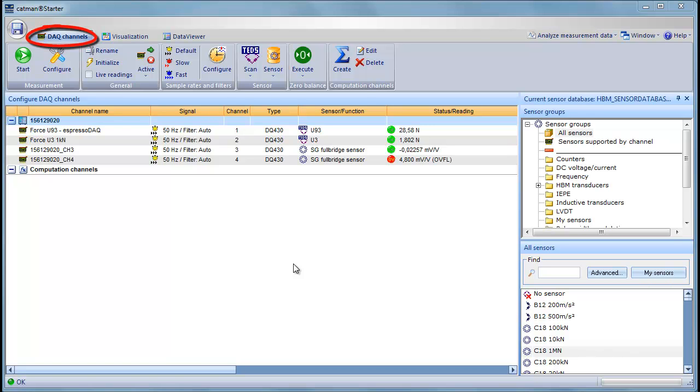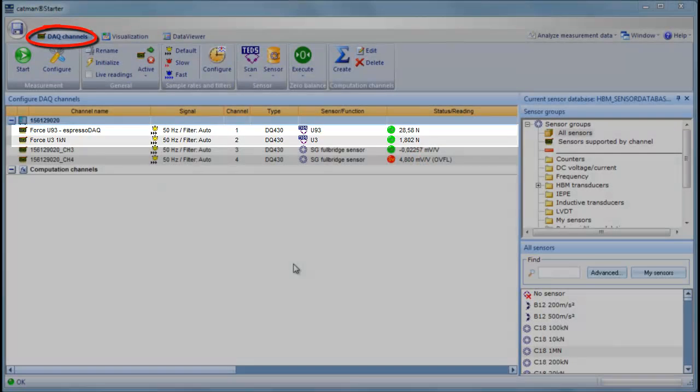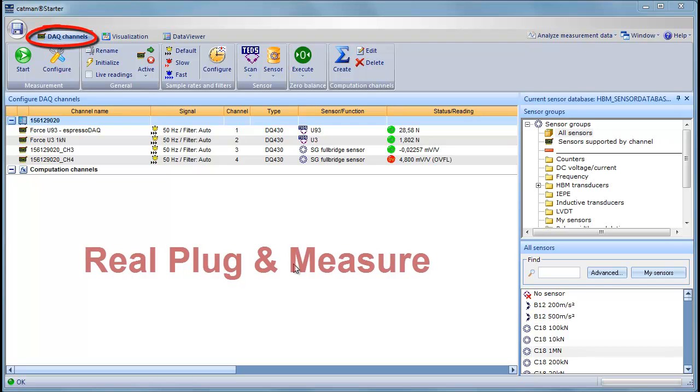As you can see, our two force transducers configured automatically, including a channel name and set of parameters from TEDs, the Transducer Electronic Data Sheet. The live value shows that we are already measuring values in Newton. The TEDs technology makes the setup easy. Simply plug in your transducers and begin your measurement. This we call Real Plug and Measure.